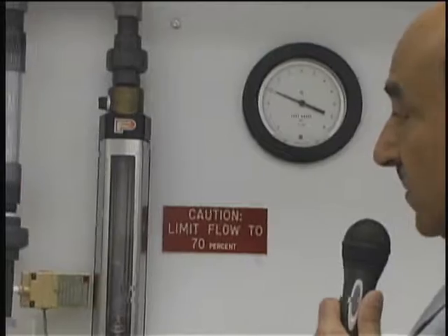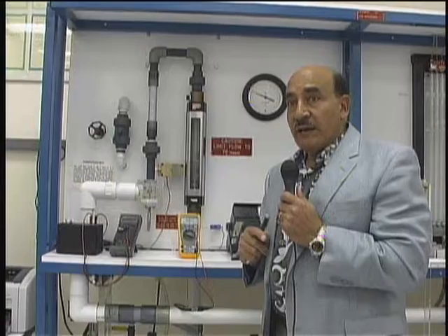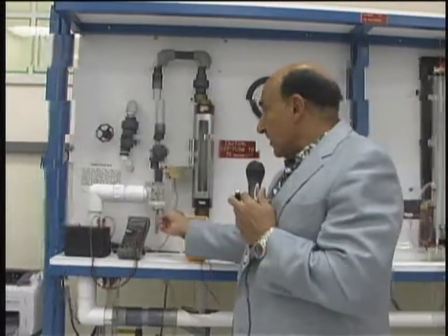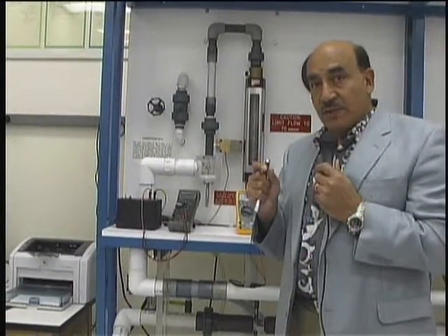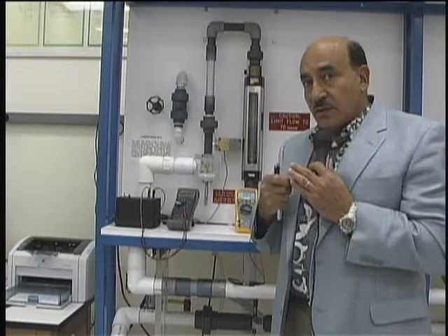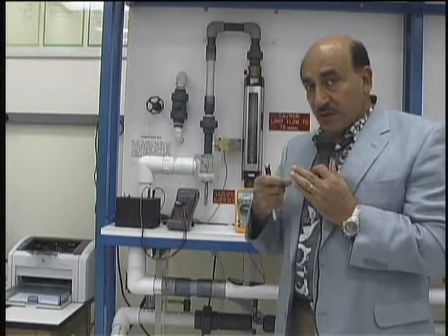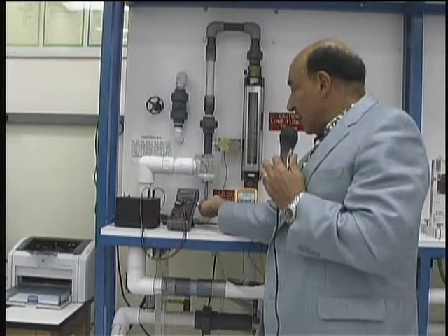Because the flow is in series, I can control the entire flow by one single obstruction, and the single obstruction is going to be the sonic nozzle. It is completely closed here, and I would like to caution you not to tighten it too much, because you can damage the seating between the cone and the cross-sectional area. That damage is plastic deformation we cannot recover, so it can introduce error in your measurement. So you have to be careful not to tighten it very much. Now we can open it.